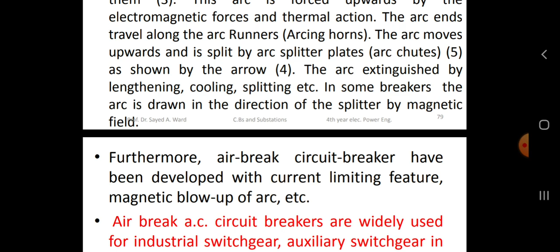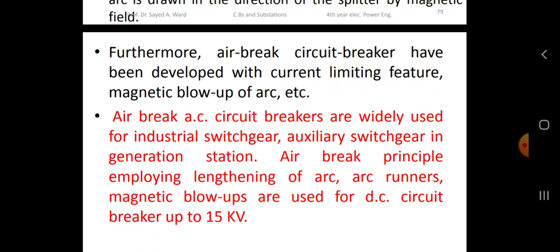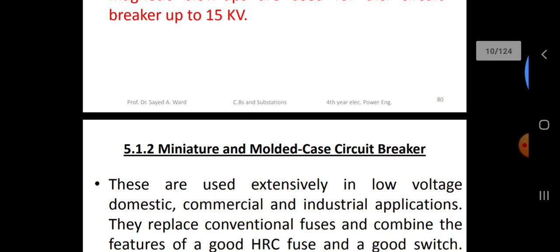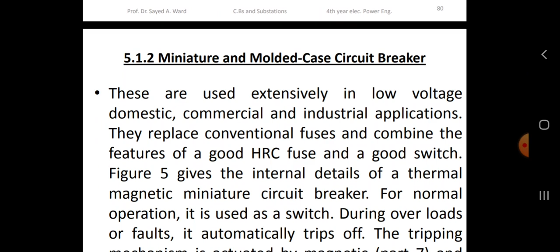Further, air break circuit breakers have developed current limiting features, magnetic blow out of the arc, etc. Air circuit breakers are widely used for industrial switchgear and auxiliary switchgear in generating stations. The air break principle employing lengthening of the arc by the runner and magnetic blow out is used for DC circuit breakers up to 15 kV. Miniature and molded case circuit breakers are extensively used in low voltage domestic, commercial and industrial applications. They replace the conventional fuse and combine the features of a good HRC fuse and a good switch.